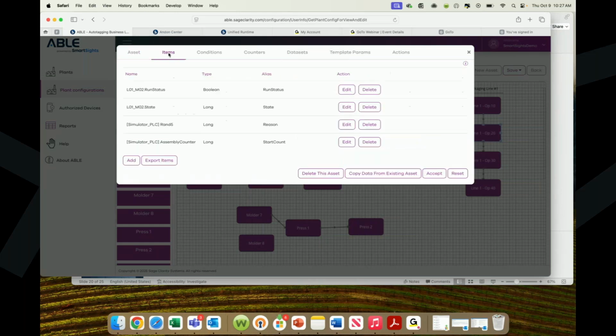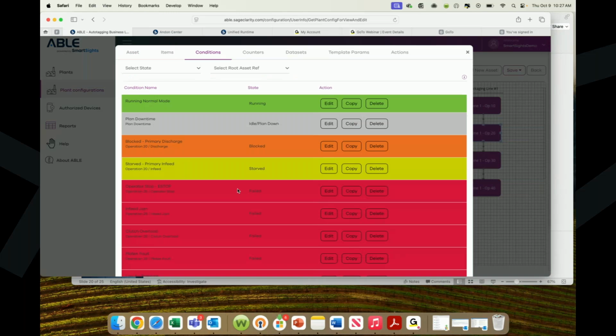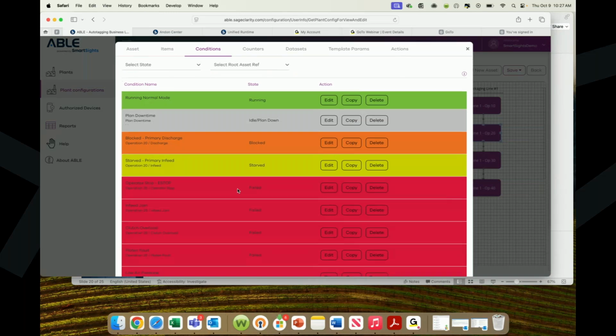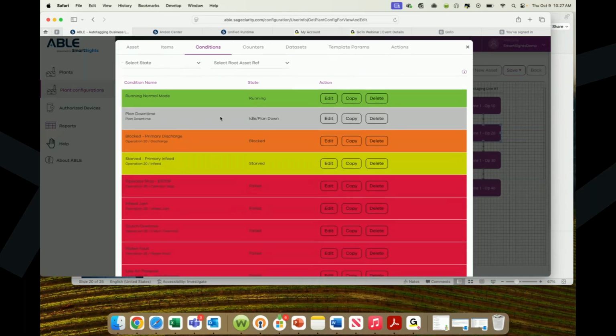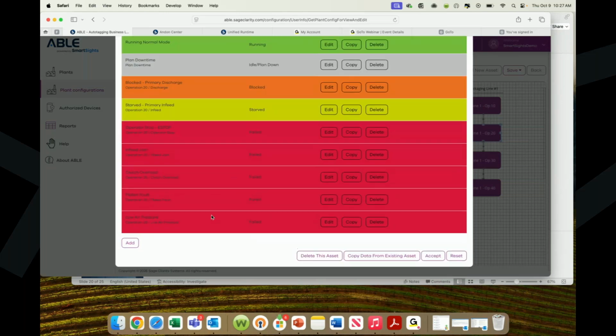Items are where we have detailed information around the state logic associated with the machine. So with Able, we identify state status as either running, starved, blocked, or faulted. This is signal information that drives that logic level. And then you have conditions, which are the meat of all this — a running condition, starved conditions, block conditions, and typically many faulted conditions.